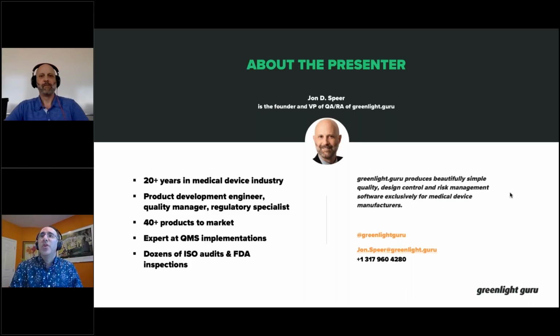Beth asks, can John also provide some examples where the medical device is software only? She has a hard time applying the design control requirements to software. Sure, that's a terrific question as well. Keep in mind that the design control regulations, defined in 820.30 and also in section 7.3 of ISO 13485, apply to medical devices.